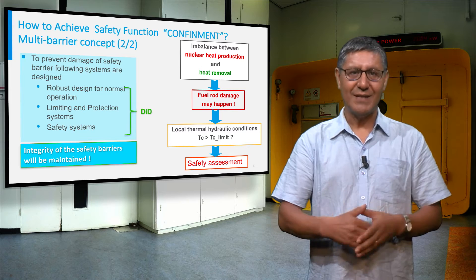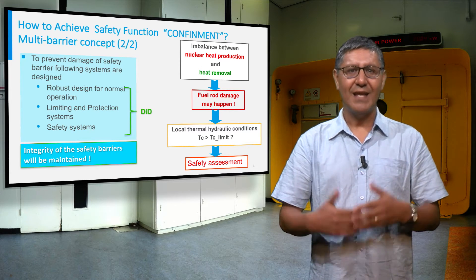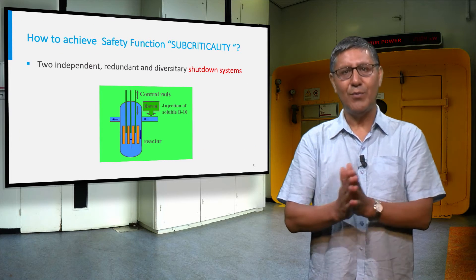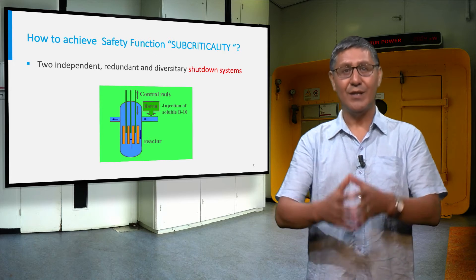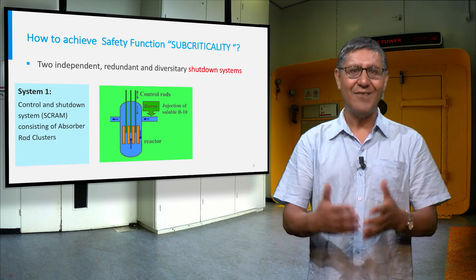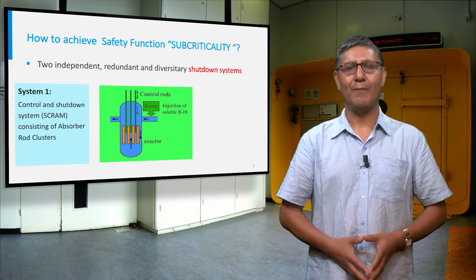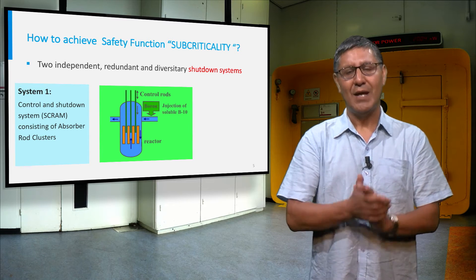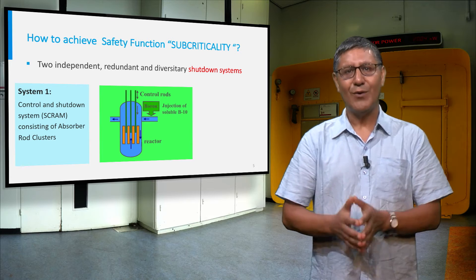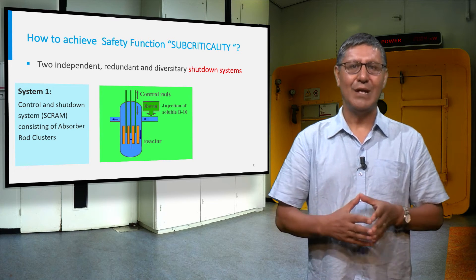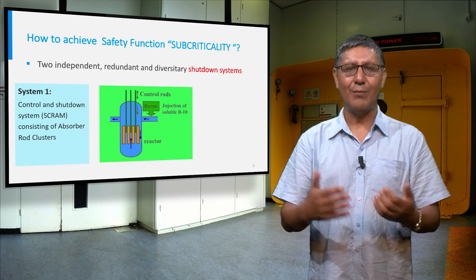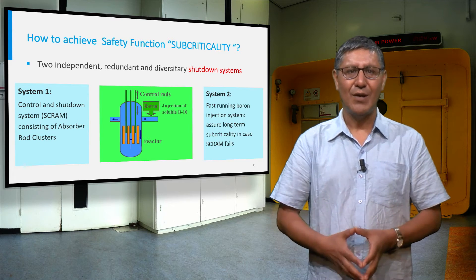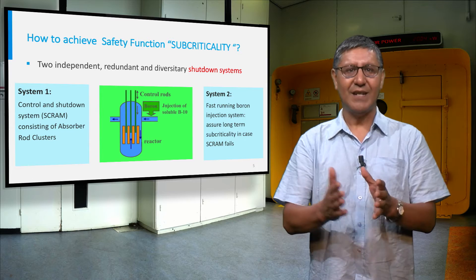Safety assessments are required to investigate the effects of these imbalances. To ensure the reactor can be brought to a subcritical state at all times, two independent, redundant, and diverse shutdown systems are required. One system consists of control rods made of strong neutron-absorbing materials such as boron carbide. The second system consists of a boric acid injection system, which ensures subcriticality if a scram fails.